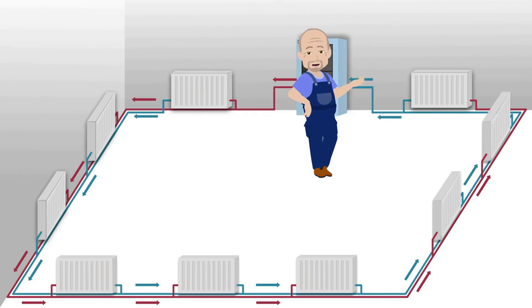After starting the whole system, let's take a look at this radiator. It's the ninth on the supply side and the first on the return. In such a setup, it turns out that this radiator has the weakest supply but the strongest return flow, because that radiator is the closest to the boiler on the return line.